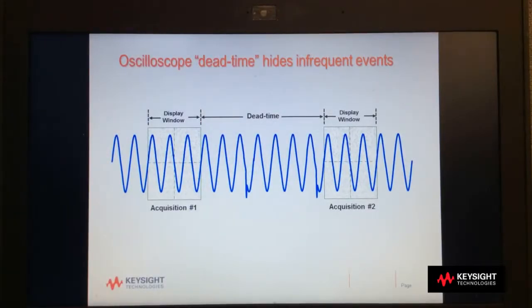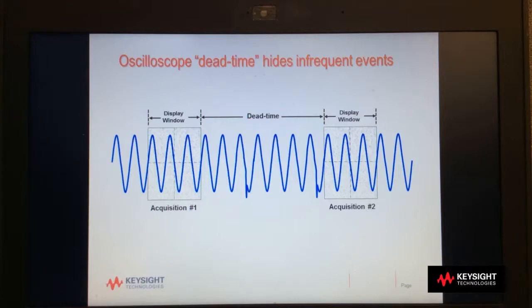Here we show an example of two acquisition cycles of an oscilloscope. Between each acquisition is oscilloscope dead time, sometimes called blind time. This is when the scope is not digitizing waveforms, but is processing the previously digitized waveform or perhaps making measurements.